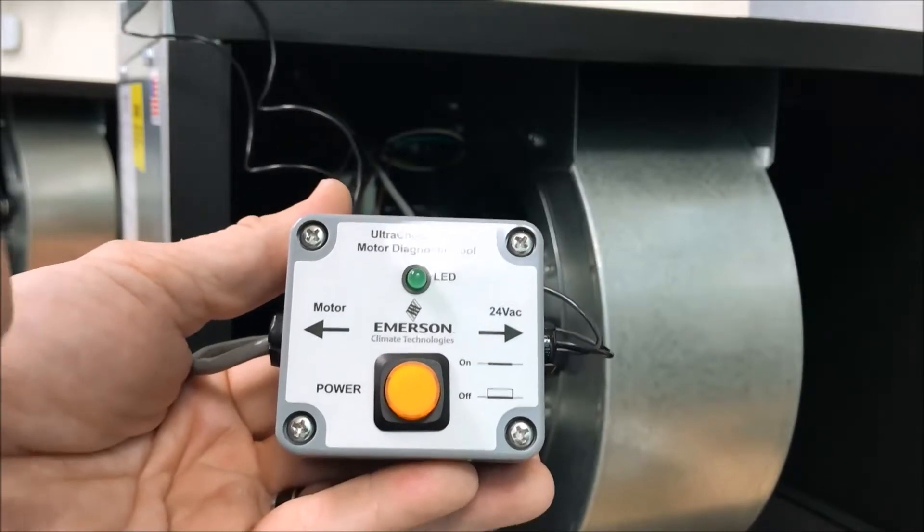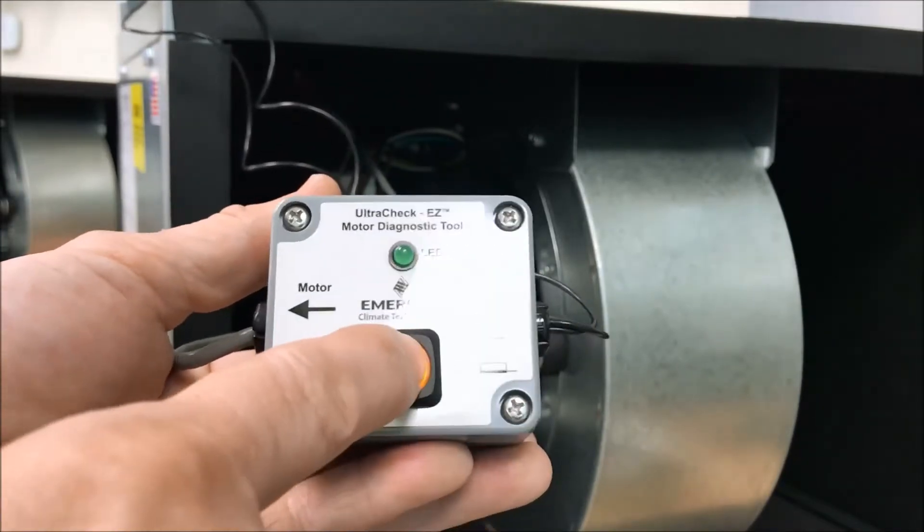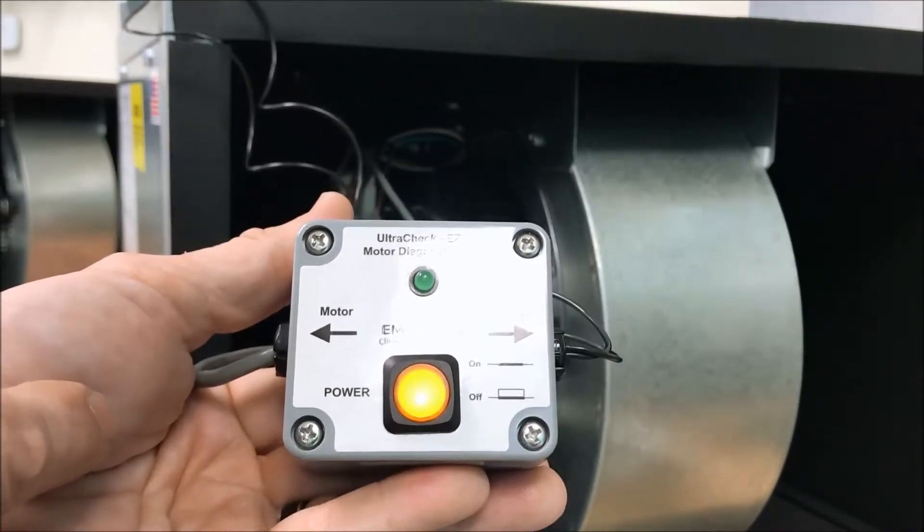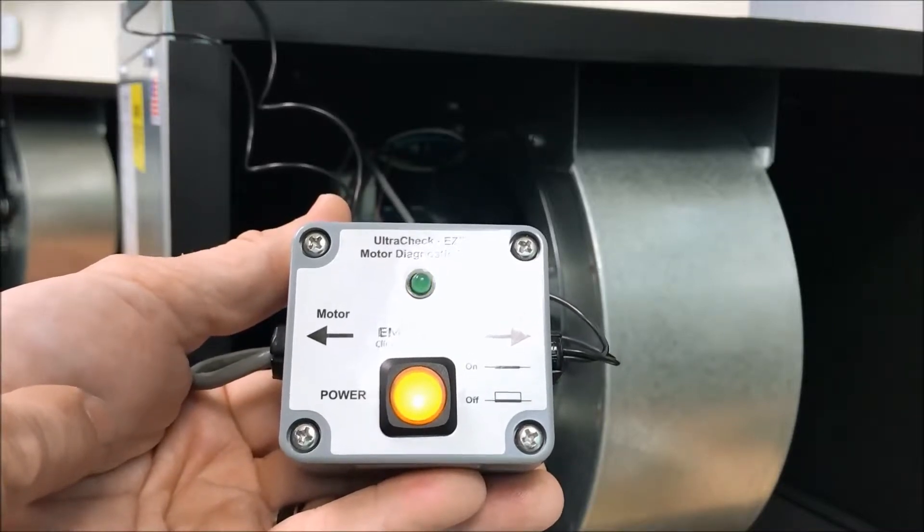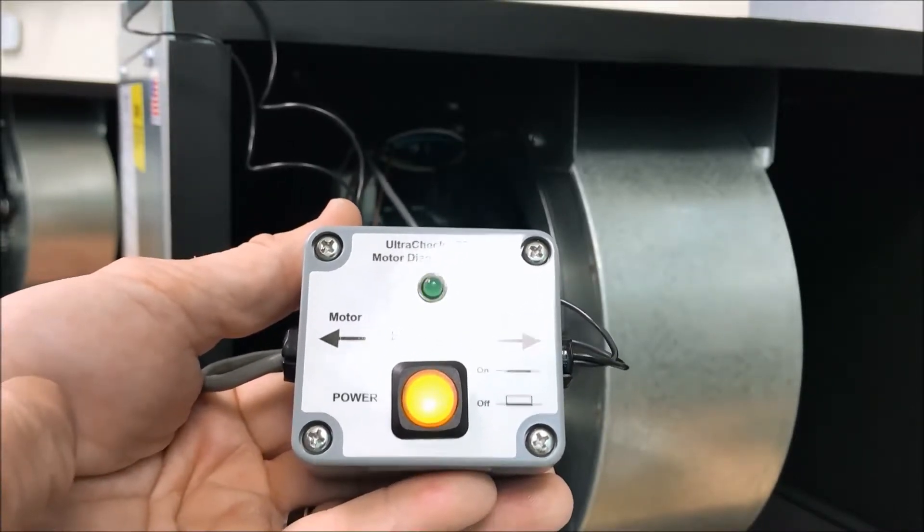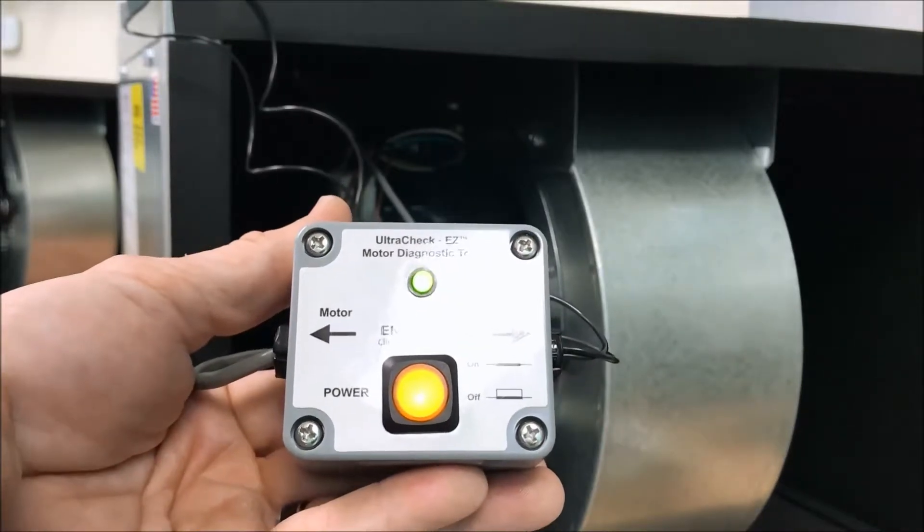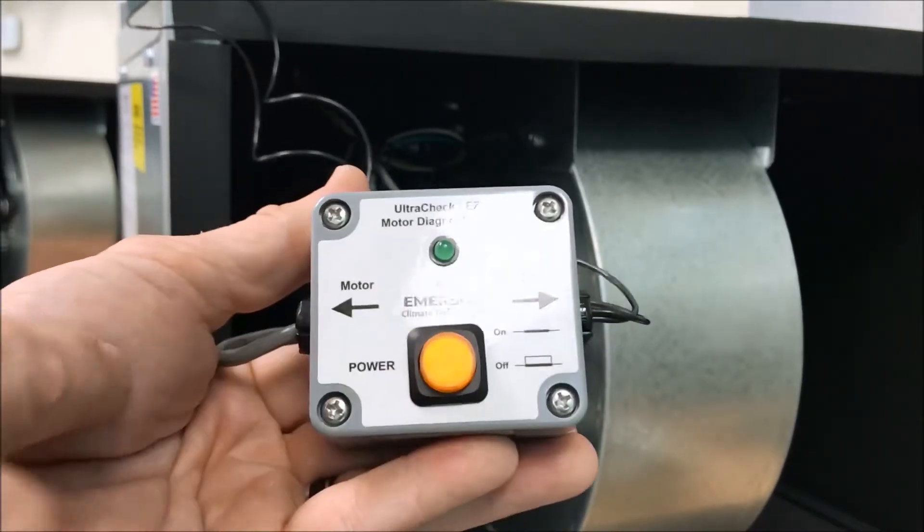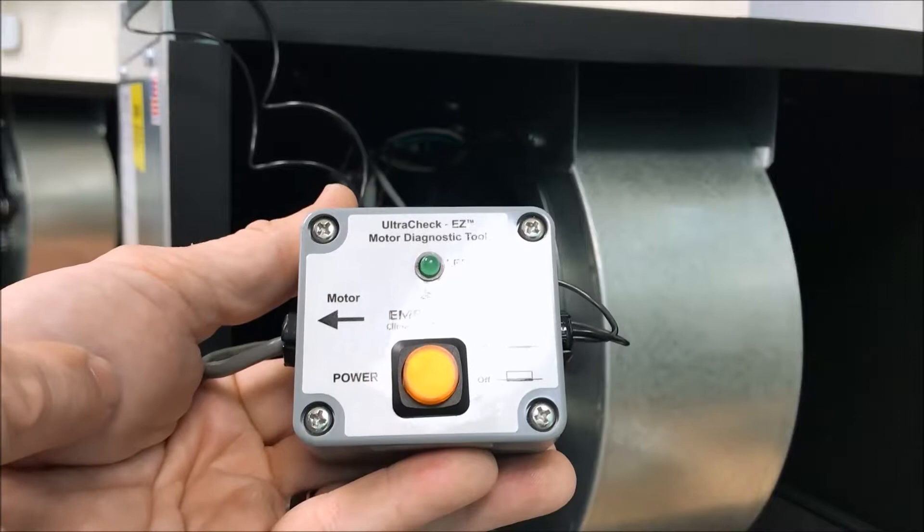You plug in the tester into the motor. You turn the tester on and within a few seconds it's going to make the motor go into the test spin. Now if the motor runs, then we know the motor is good. Replace the board.